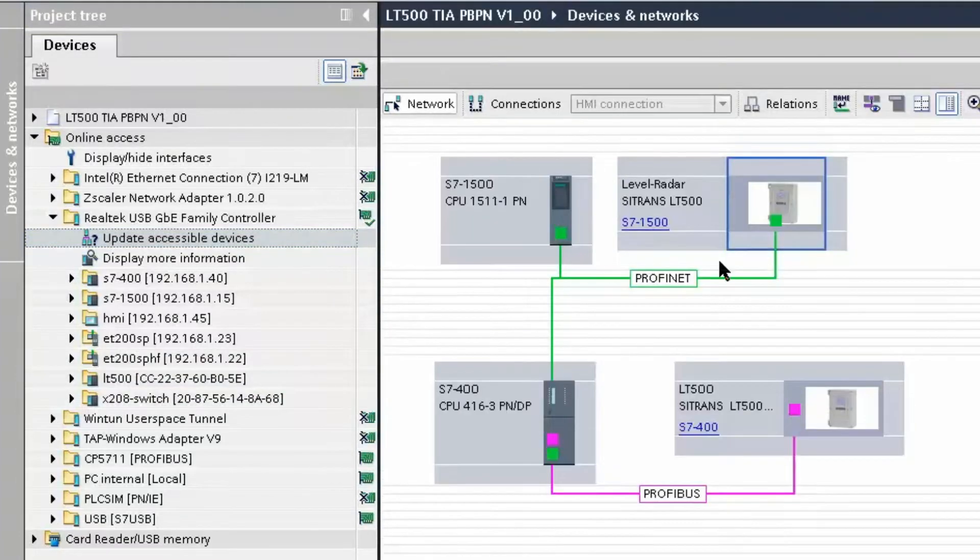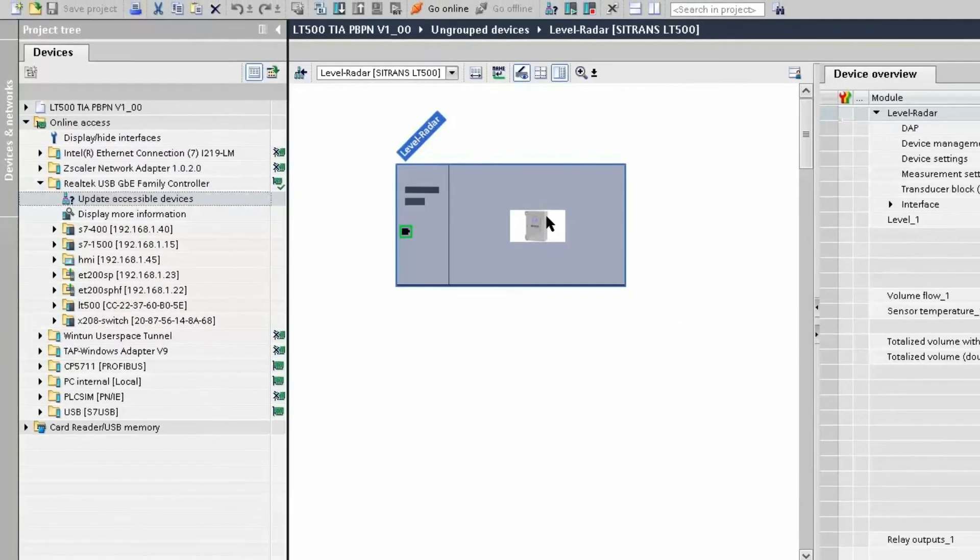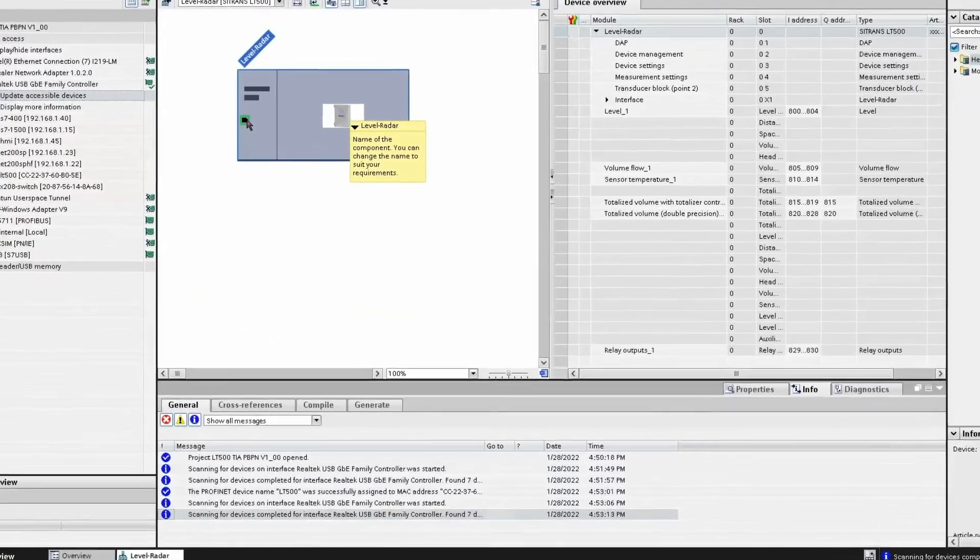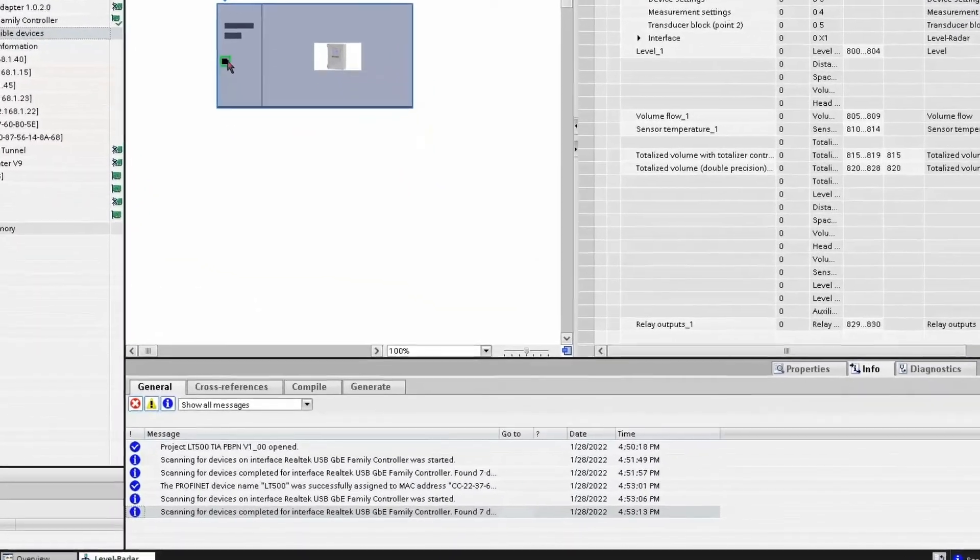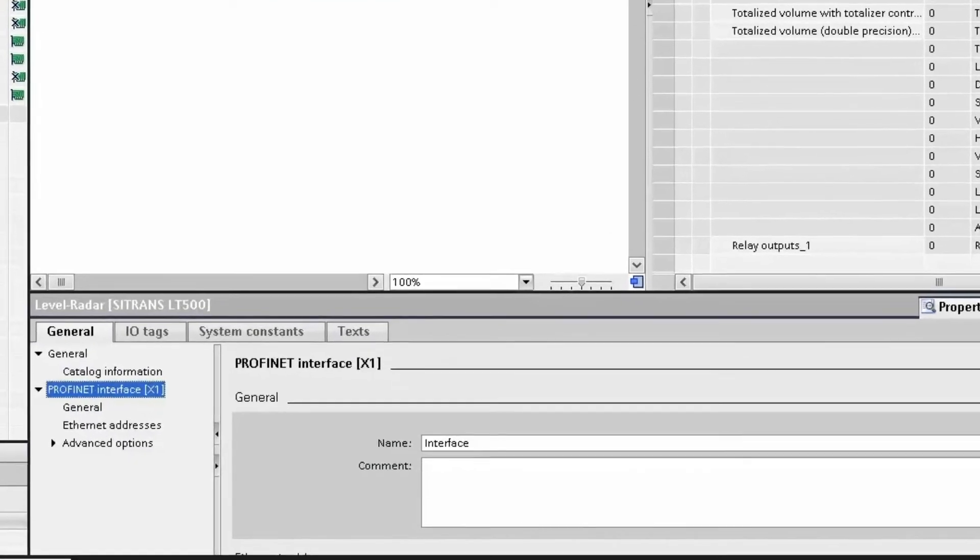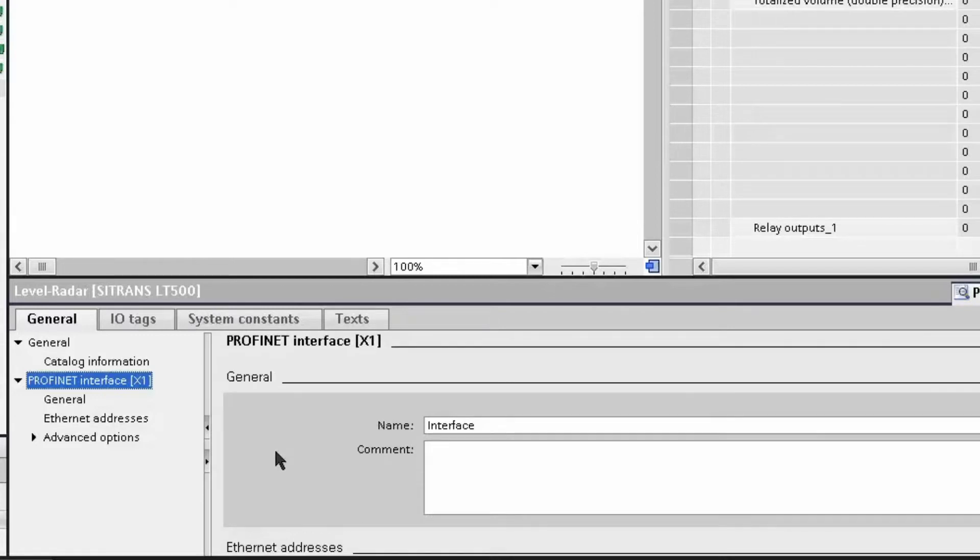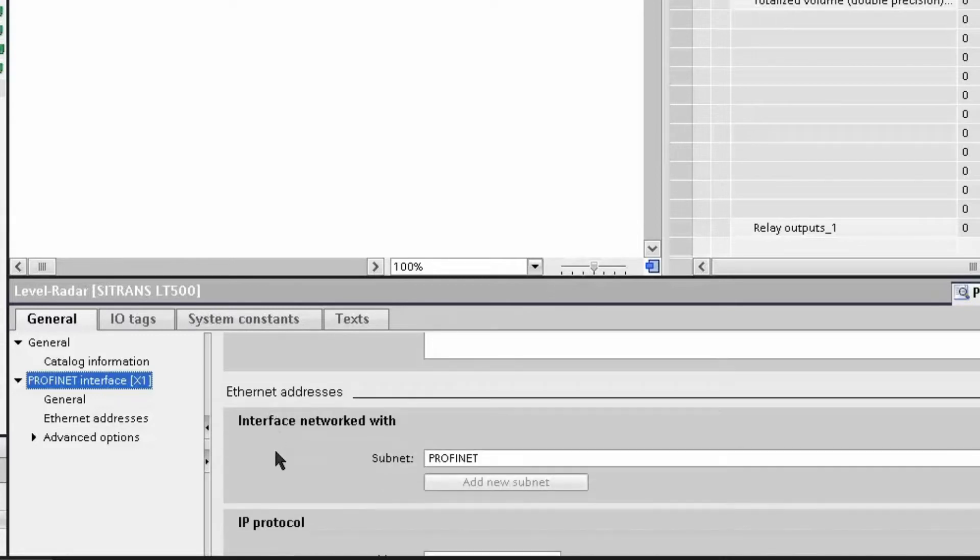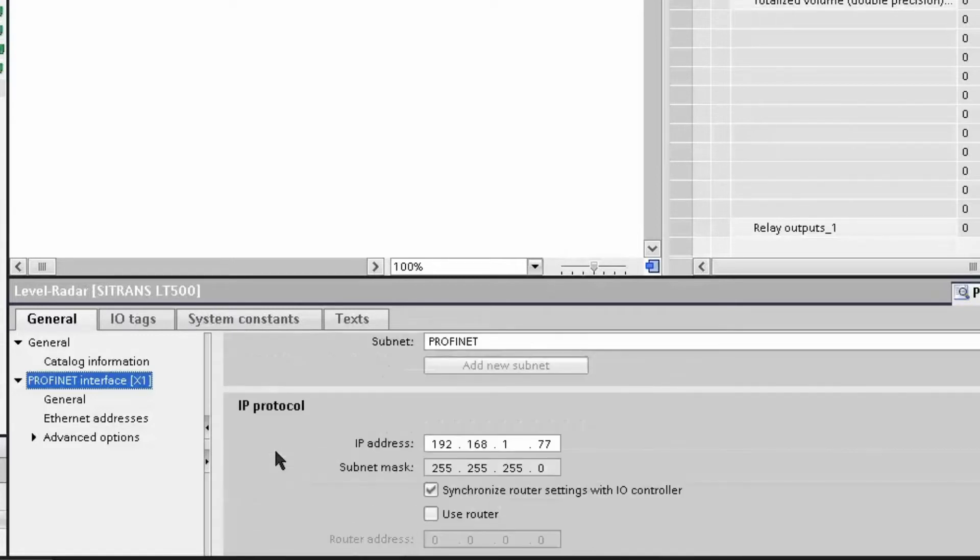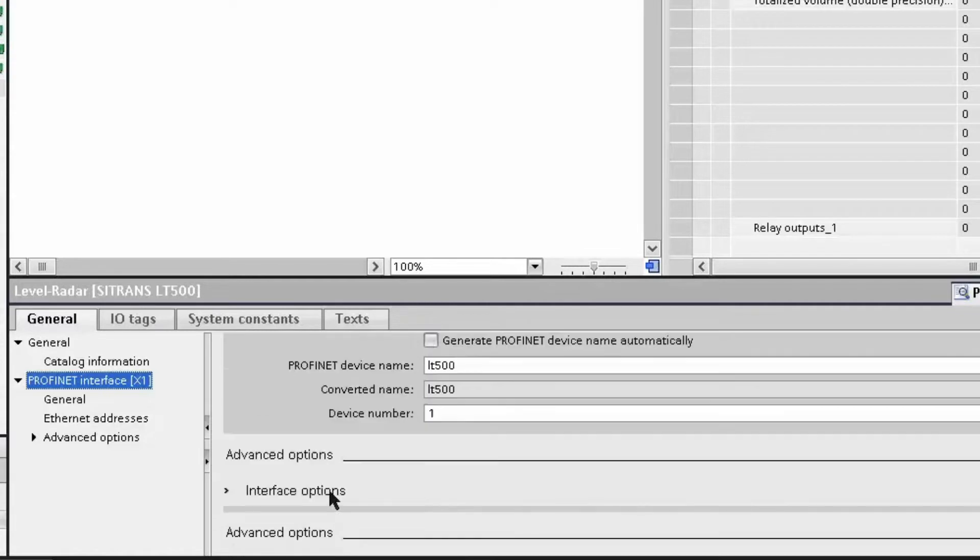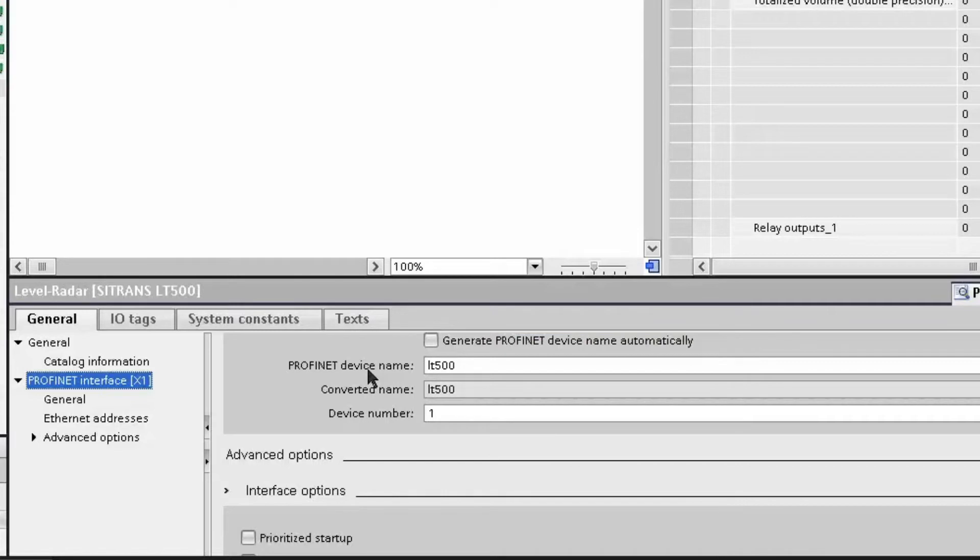For now, let's see what a working system would look like. If we look at the LT500 connected to the S71500 via ProfiNet and we take a look at the properties, we will notice that our project has an IP address already assigned. This IP address will be used by the IO controller and sent to the LT500 after the IO controller has found the device by its device name.